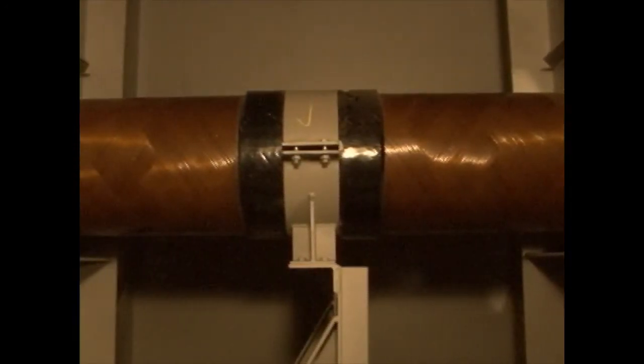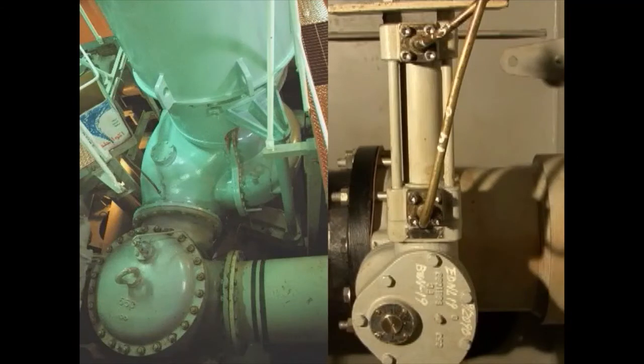If flow velocity within the pipeline suddenly changes due to valve operation at the start of or during pump operation, the pipeline internal pressure increases momentarily but sharply. This phenomenon is called water hammering. Water hammer can damage the pump casing, valves and pipeline.